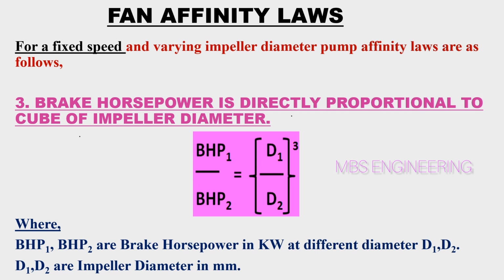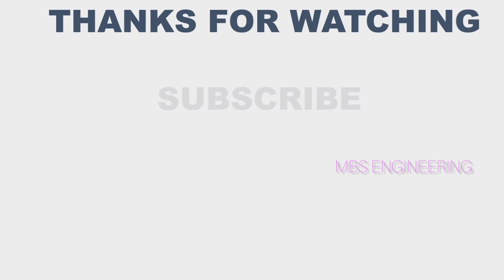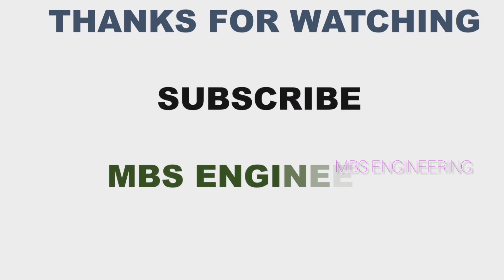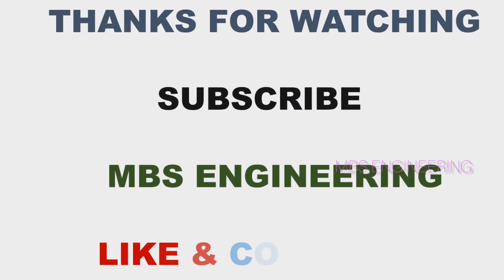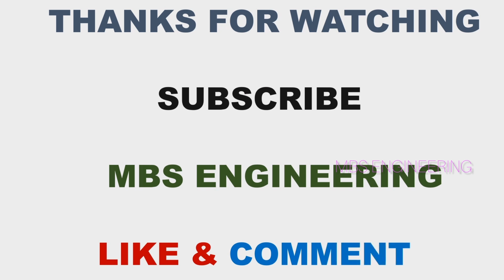We hope everyone understands the pump affinity laws. These laws can be used to calculate the resulting flow rate, head, and power consumption when either the speed is changed or the impeller diameter is constant. They can also be applied when the impeller diameter is changed while the speed remains constant.